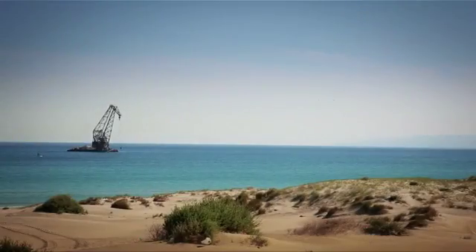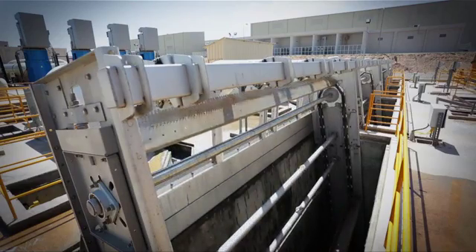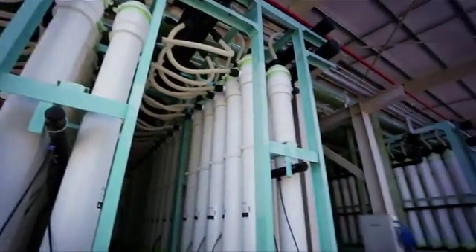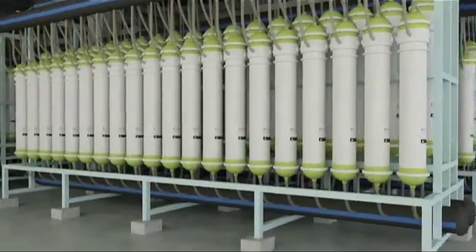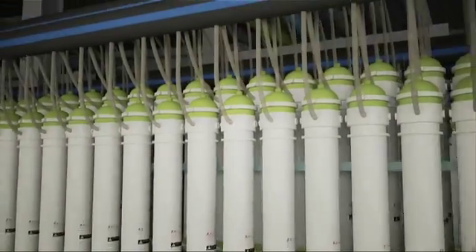In desalination, seawater undergoes a series of treatment processes before it is turned into fresh water. First, debris and large particles are removed by a series of intake filter screens before the seawater is pumped to the ultra-filtration pretreatment system. The Magtaa Desalination Plant features the world's largest ultra-filtration pretreatment installation, comprising Hyflux's award-winning Kristal membranes. Kristal ultra-filtration membranes are able to filter out the smallest impurities such as micro-suspended solids, microorganisms, bacteria and even viruses from the salt water. The water leaving Kristal membranes is of consistently high quality, which helps to maintain the efficiency and preserve the lifespan of the reverse osmosis membranes.